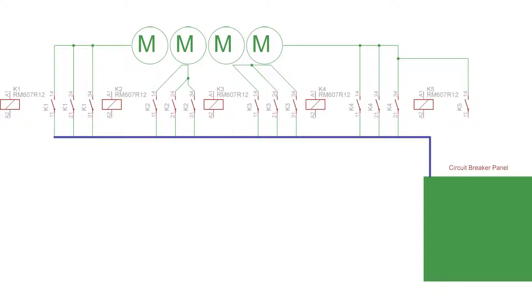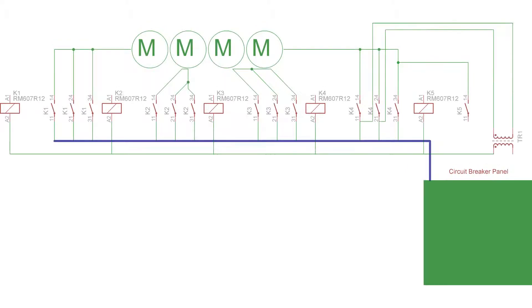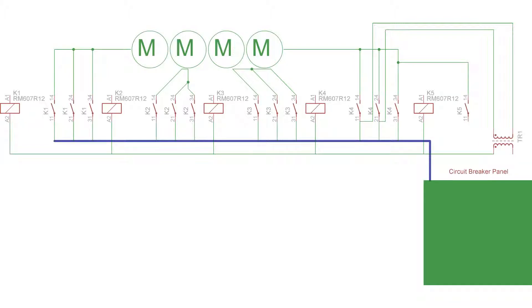So from these contactors they're all ran into this circuit breaker box. Now you may see the big fat blue line that's not a wire that's a busway. So just pretend that's a big fat cable holding all the individual wires running into the contactors. Now I ran one side of the control leads on the contactors to the low voltage side of my transformer. This is basically the common. Now the other side of the transformer, the high voltage side, ties into the motor one circuit breaker. Now this means if motor one circuit breaker trips it kills the whole thing.